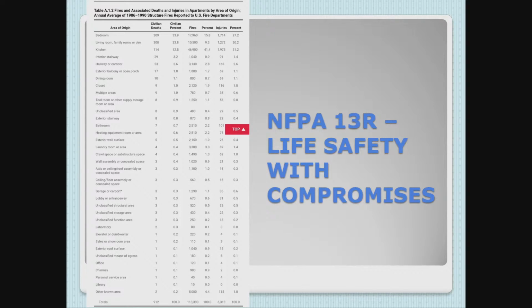And then they took all these numbers and they said, okay, we've got to give up something. And they pretty much drew a line and they said, okay, we're going to make sure that the areas where fires occur that cause death and injuries, they're going to get protected with sprinklers. But the areas that are less frequent for fires, and more importantly, less frequent for deaths and injuries, like your garage or carport, an outside stairway, a lobby, an attic. So look, during this time that they evaluated this for 5 fire years, attic or roof ceiling assemblies, they only had 3 civilian deaths. So you know what? Sprinklering an attic is expensive.